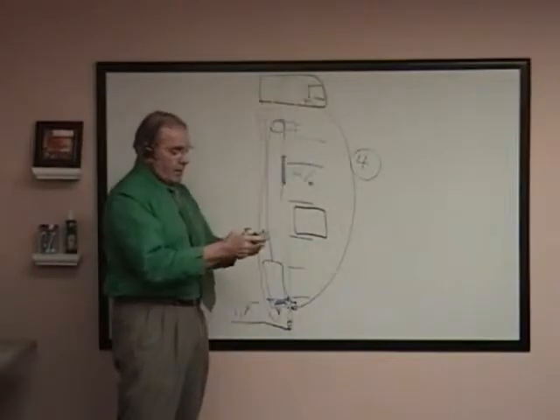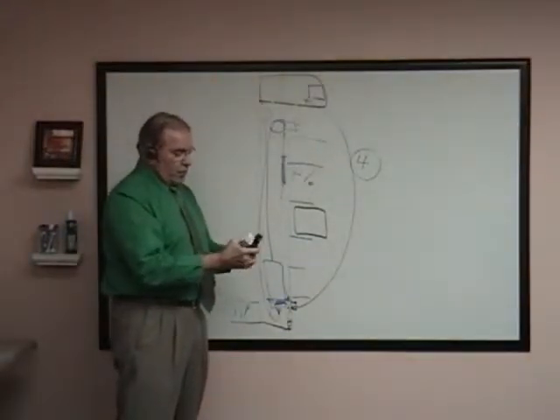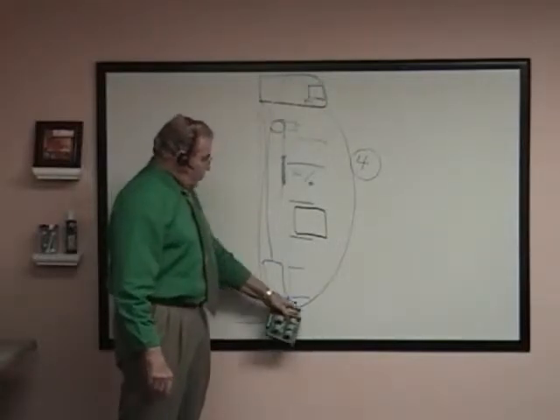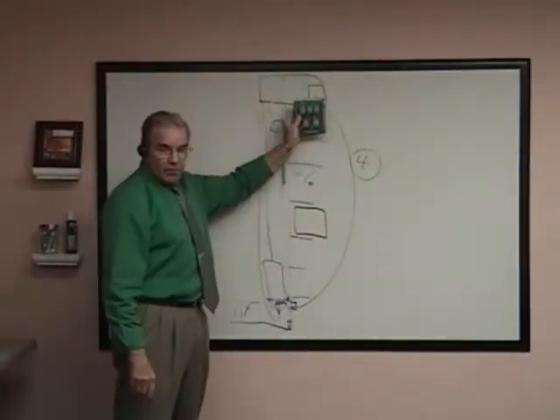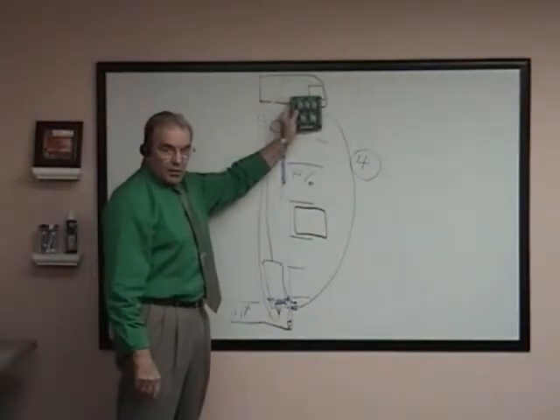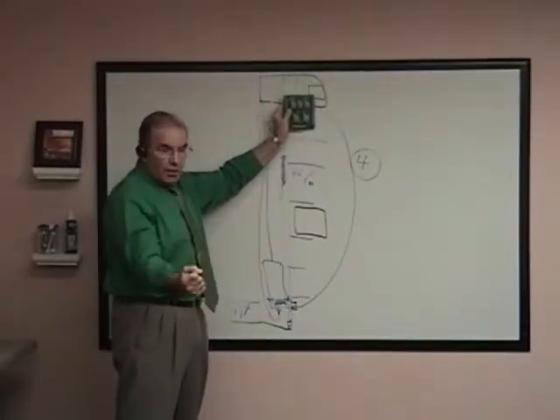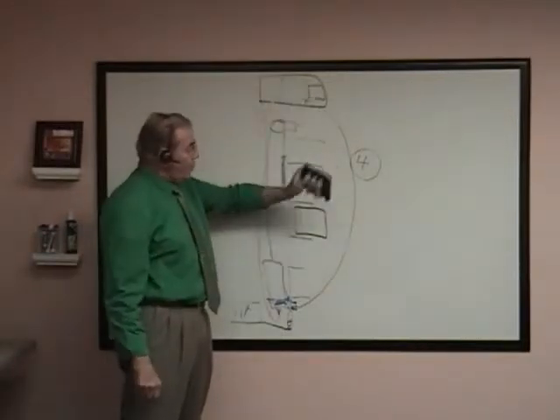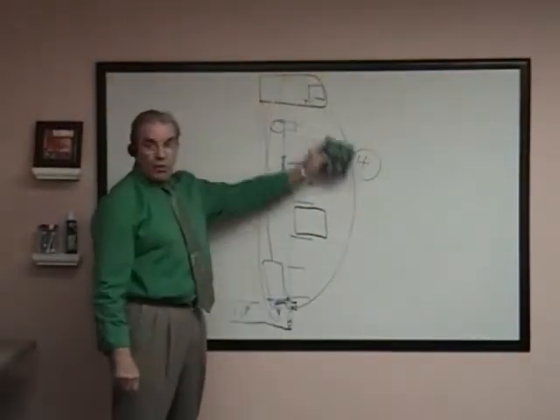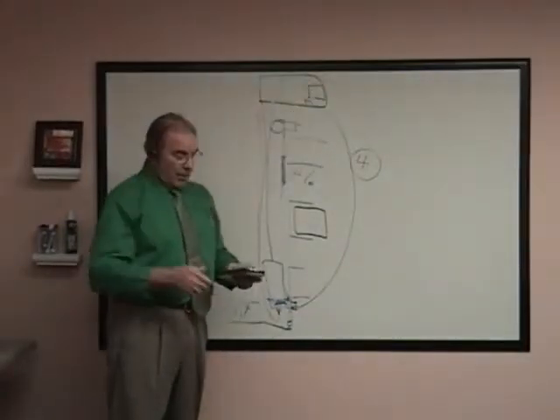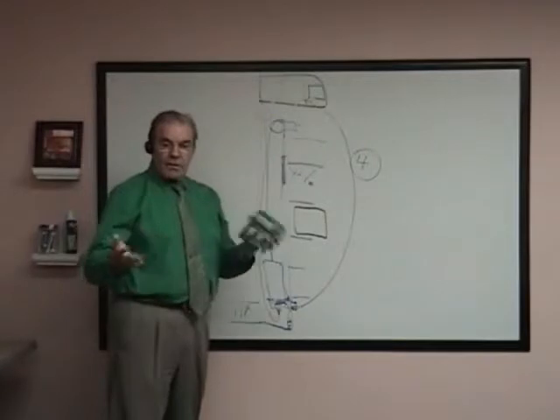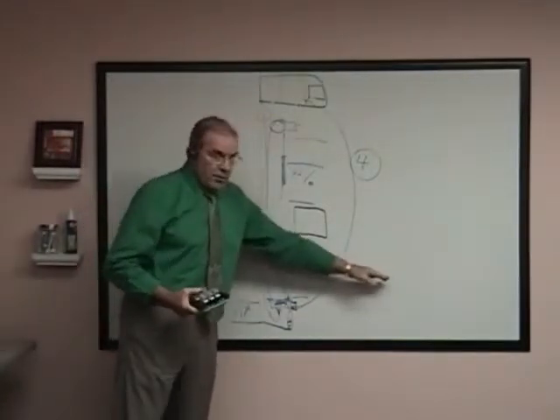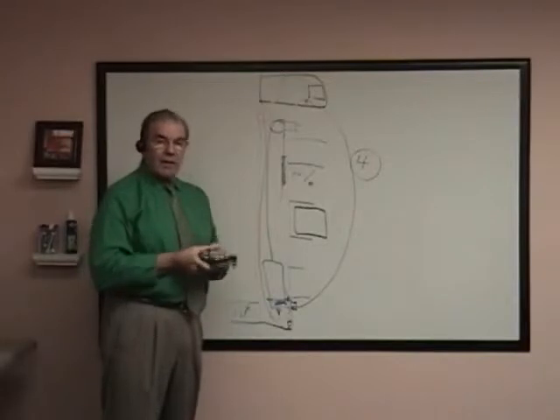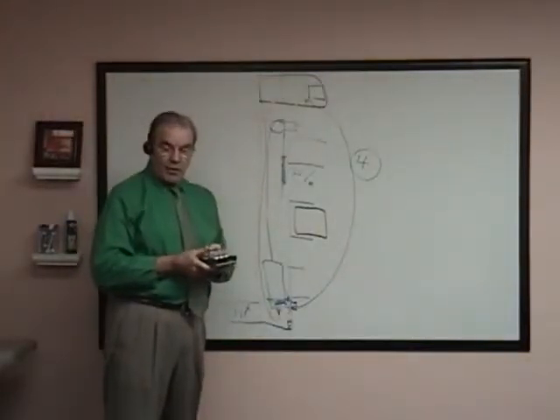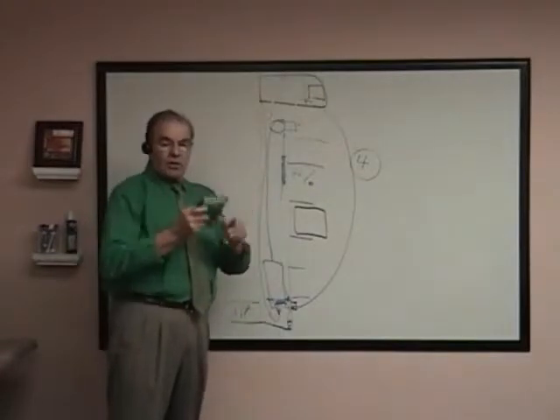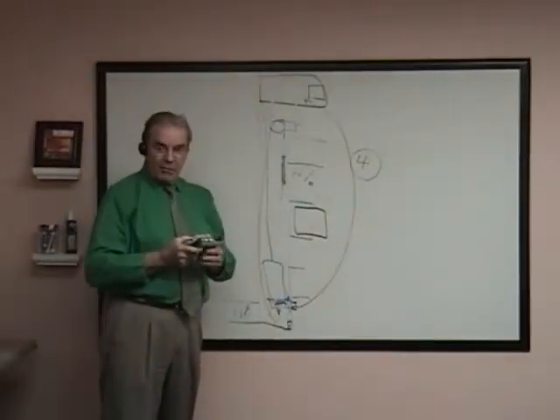once this board sees a water intrusion signal, this board will lock itself in place and will stay that way until someone goes to the machine room and physically resets the main line, which drops the relays out on this board and allows the system to go back into normal operation. That's one thing. But we designed this board with an option. Let's say that the mechanic, maybe he's got 10 cars. He's got these on all 10 cars. And he's saying, wow, if I trip all 10 cars with water, I have to walk to the machine room.